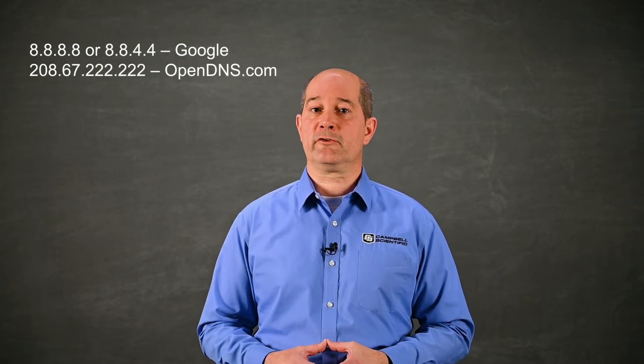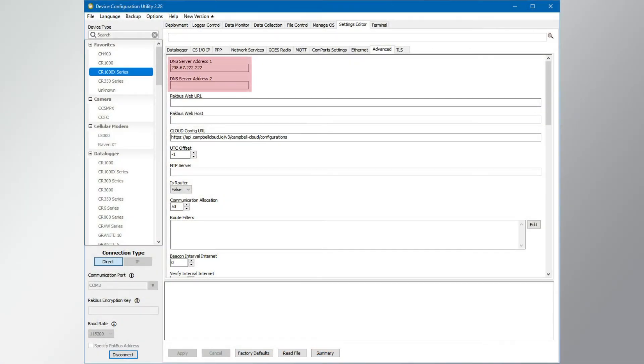With an understanding of how IP addresses work, I will discuss using domain names to make devices easy to find. Domain names like campbellsci.com are easy for people to understand, but computers require an IP address. To get the IP address, the computer connects to a DNS server — a domain name system server — which translates the domain name into an IPv4 address, similar to a telephone book. Common DNS servers include 8.8.8.8 and 8.8.4.4 for Google, and 208.67.222.222 for OpenDNS. Use the device configuration utility to view the DNS servers the datalogger uses, found in the advanced tab of the settings editor. Without a DNS server, a datalogger has no way to resolve a domain name to an IPv4 address.